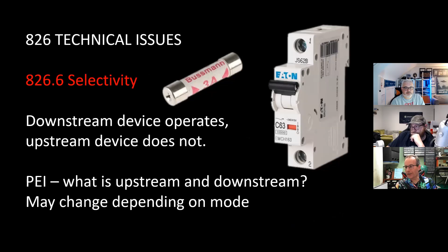Now, selectivity, called discrimination until fairly recently. The principle is that your downstream device operates, so that would be a 3 amp fuse, and the upstream device, as in your circuit breaker there, 63 amps, does not. So that's fairly well established. However, in a PEI, what is upstream and downstream, bearing in mind you've got current going both ways? You've got different sources of energy coming in. So where are you going to put your protective devices and how are you going to ensure selectivity between them? And bearing in mind the direction of the energy can change depending on what mode you're in.